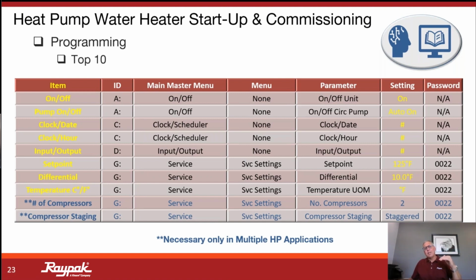And staggered will look like this. And I'll have a better example in a diagram. Let's say we have 4 units in Cascade and we have a single storage tank. The staggered selection there will say that if I have a 10-degree differential, right? If I fall that 10 degrees from 140 stored water temperature, I fall to 130, bring on all 4 units. And all 4 units are going to stage and stagger equally at about 2.5 degrees. 2.5 degrees times 4 units will give me that 10-degree differential.